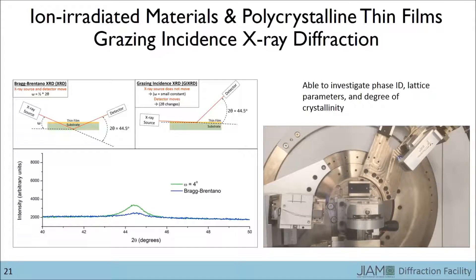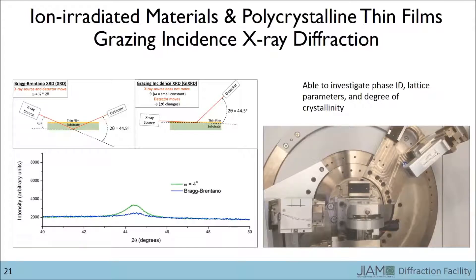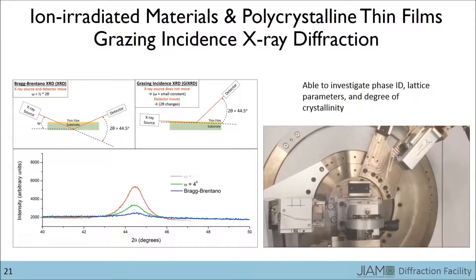We now remain in the grazing incidence configuration, but the grazing angle is reduced to 1 degree and the detector moves to 39 degrees. Again, the detector rotates by 10 degrees to bring the total end angle to 50 degrees, and we see the peak intensity has continued to increase.